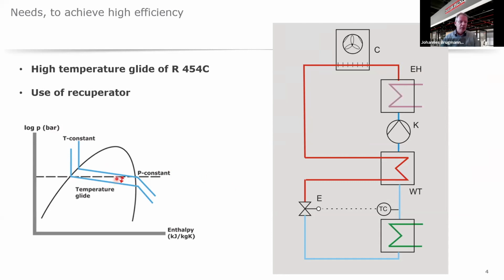side. You also have the possibility to use this glide effect if you have a recuperator, for example, and that's not new, that's a quite old common technique for R407C that was used, or is used today, with a GWP of around 1,700. And if you use this temperature glide, you can also increase the efficiency.